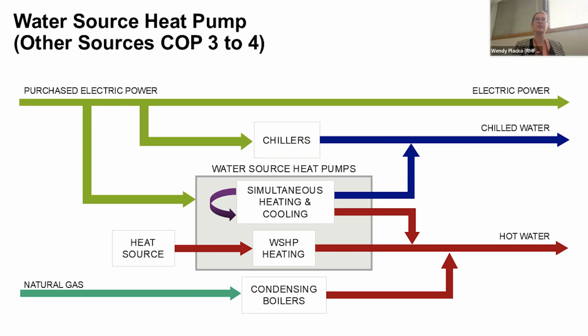Let's continue talking about the pros and cons of a water source heat pump and how that fits into the schematic. The way this works is very similar to the heat recovery chiller, because you're still taking advantage of those simultaneous heating and cooling modes, which you might do with a separate piece of equipment or the same piece, but there's no reason not to do that. Your heat pump is going to take heat from wherever it has available, so you can see how these interact.